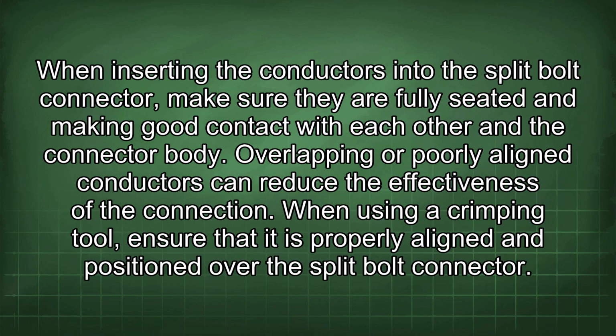When inserting the conductors into the split bolt connector, make sure they are fully seated and making good contact with each other and the connector body. Overlapping or poorly aligned conductors can reduce the effectiveness of the connection.